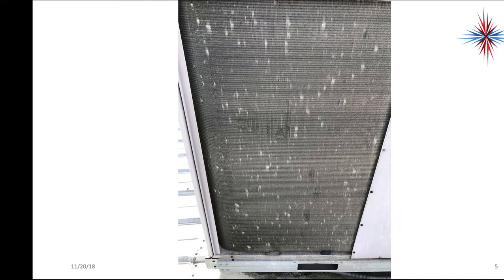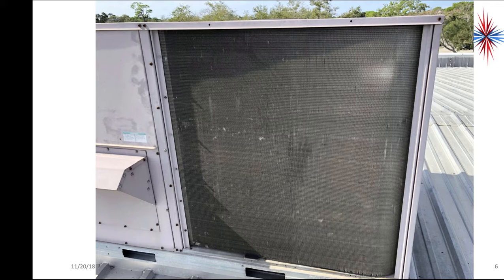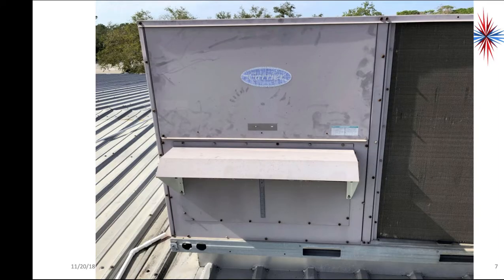Look at the condenser coil. We want to look at all sides of the coil. From the outside, we do see some wind and debris related damage. This sits next to an airport, so that's really not surprising. It's pretty wide open. And the unit's a 2003, if I remember right. Look at the other side of the condenser coil. Really nothing unusual there.